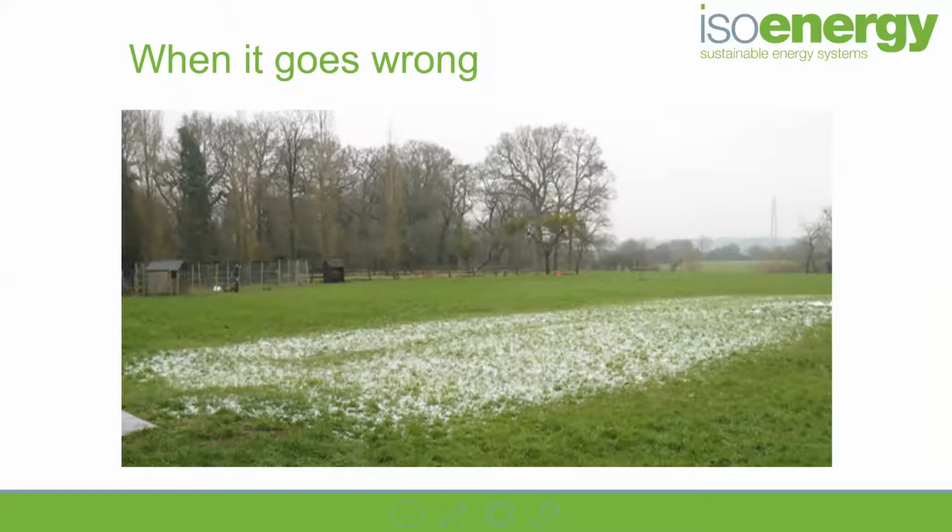Now, if you reduce the amount of area that you're taking energy from, then you will increase the temperature deficit, the delta T, in that localized area. And by increasing that, you're taking out more energy, and then the temperature will start dropping. So if you're taking out 3 degrees per year, there's 100% chance that that energy will recover over the summer as the ground temperature goes from 8 degrees in the winter to 16 degrees or so in the summer.